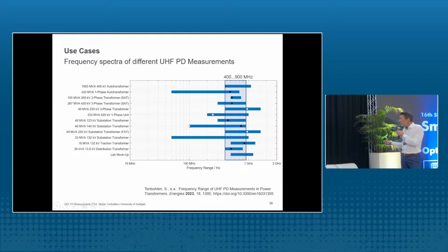And it shows in which frequency range they measured the PD. For example, let's look here at this 333 MVA transformer. Yeah, there are frequencies from below 100 megahertz up to 1 gigahertz measured. So a large frequency band. The dots here mean that at this frequency we have the highest emission, but more or less you can say that in the range of 400 to 900 megahertz, all PD emitted electromagnetic waves. Yeah, so if you measure in this frequency range, you can be pretty sure that you will detect the PD.